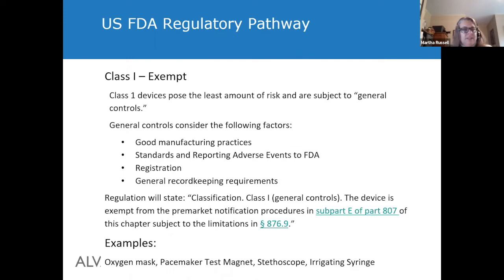So class 1 exempt, similar to what I've already said. Some of the general controls that you need for a class 1 exempt: good manufacturing processes, adverse event reports. You're going to need facility registration, so the FDA knows where to find your manufacturing location, for those audits that we talked about. And general record keeping requirements. So you want to be able to have a quality system and a document control system. So you want to be able to prove that if you would be audited by the FDA.